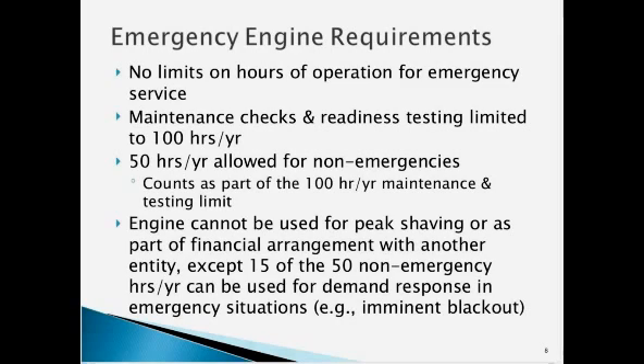And part of that 100 hours, the rule says you could use 50 hours for non-emergency purposes, but that cannot include peak shaving or any kind of operation as part of a financial arrangement with another entity, except that 15 of those 50 hours can be used for emergency demand response, for example, an imminent blackout.